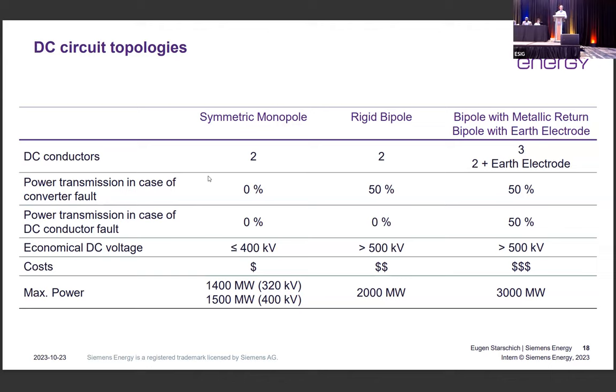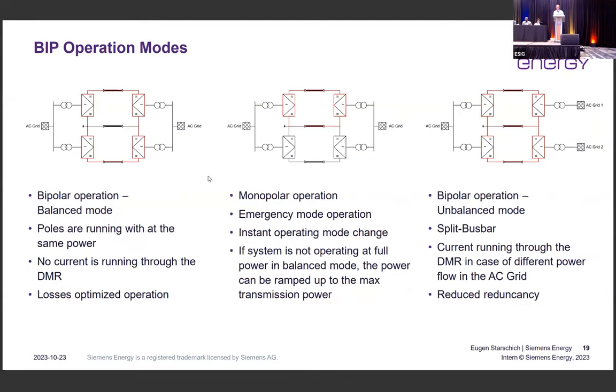And as I said, it's mostly limited due to the single contingency or the DC cable limitations. For the rigid bipole and the bipolar configuration, the most common DC voltage that we're using is more than 500 kV, 525, 600 kV, depending on the requirements. But then also the maximum power that we can reach with the bipolar system is more than 3 gigawatts.